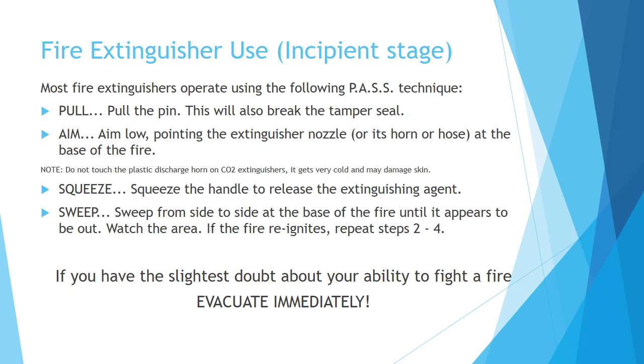Aim: you aim low, pointing the fire extinguisher nozzle, horn, or hose at the base of the fire. Note: do not touch the plastic discharge horn on CO2 extinguishers. It gets very cold and may damage the skin. Squeeze the handle to release the extinguishing agent, and sweep from side to side at the base of the fire until it appears to be out. Watch the area. If the fire reignites, repeat steps 2 through 4. If you have the slightest doubt about your ability to fight a fire, evacuate immediately.